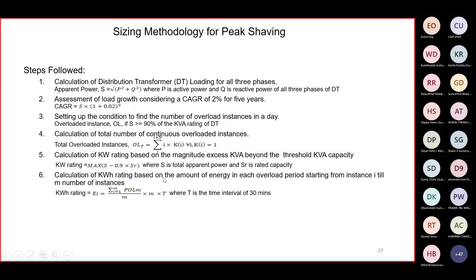We first took the loading of a distribution transformer, then applied a CAGR of 2% for 5 years, and calculated the continuous overloaded instances happening in a day. We then came up with the maximum kilowatt reached in those continuous instances, and the time duration, whether 1 hour or 2 hours, which helped us arrive at these sizes.